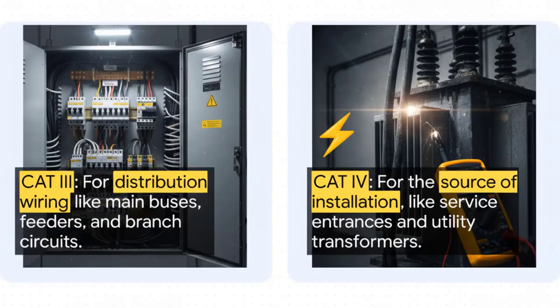Rule number 1, and don't you ever forget it, is CAT ratings. This isn't about voltage, it's about energy. CAT 3 is for your regular branch circuits. CAT 4 is for the service entrance, where the utility power comes in. That's the highest energy environment. You bring a CAT 3 meter to a CAT 4 fight, and you are going to lose catastrophically. That Fluke 87V is rated to survive an 8,000-volt transient. That is what you are paying for: survival.